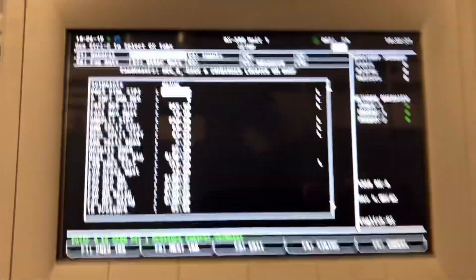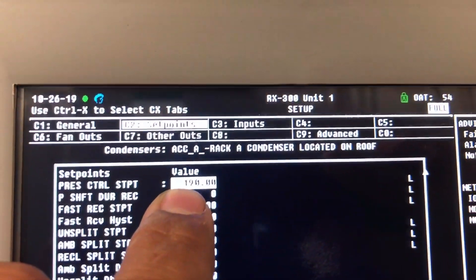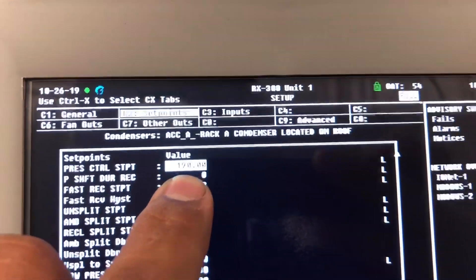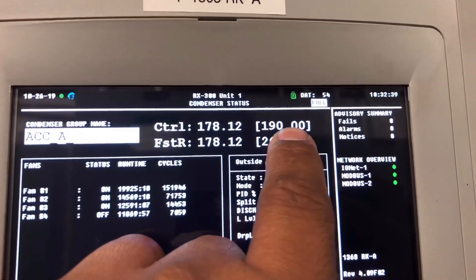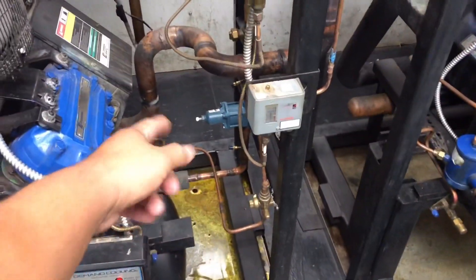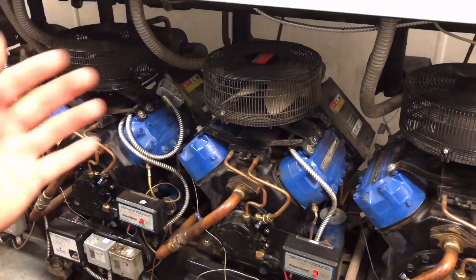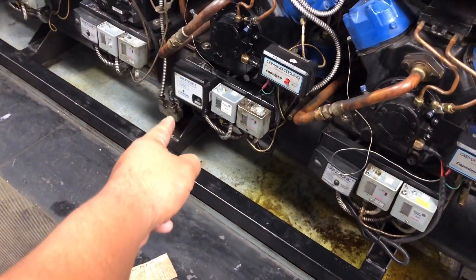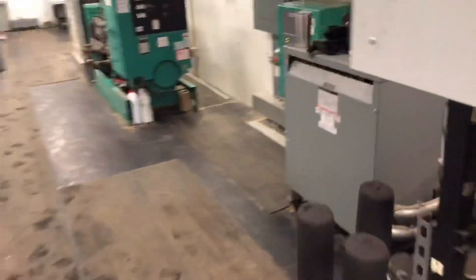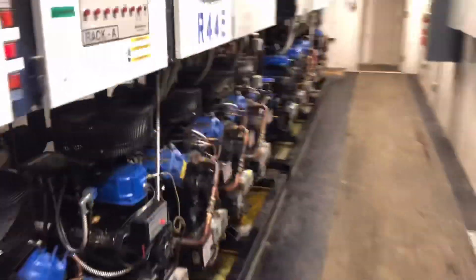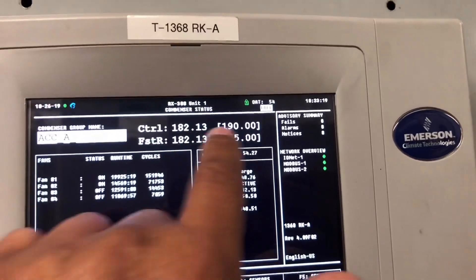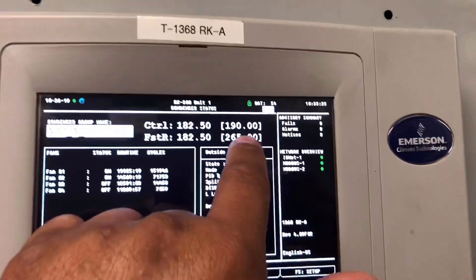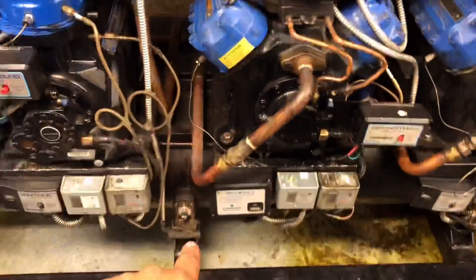This is what we're doing now. Pretty much what I did was, our set point was 177, so now we're going to raise that up to 190 on the discharge. Pretty much what that's going to do is we're going to start cycling off fans. We get to about 190 psi, we're going to raise our discharge, we should raise our drop leg, raise our temperature so the cool gas going to the cases is warmer and we can defrost cases faster and possibly not fill up as fast. I've been on the phone with my supervisor and the top tech and all that good stuff. As you can see, we're shutting fans off now, we're trying to get this pressure up to 190.